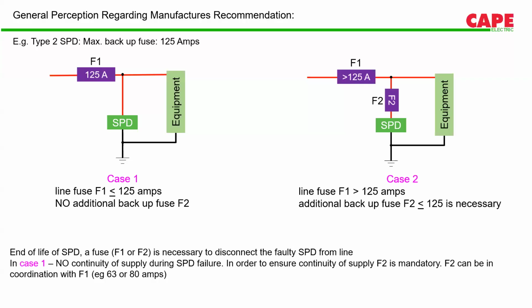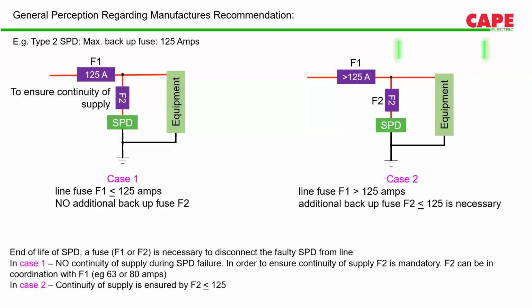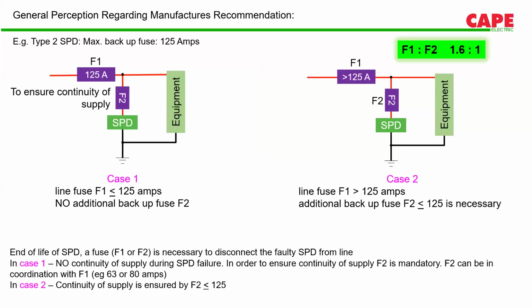Whereas in case number 2, once the SPD fails, only F2 will blow and F1 will remain in closed mode. So we get continuity of supply. So there are two things. One is priority to continuity of supply. Second is priority to continuity of protection. In case number 1, we are getting a priority to continuity of protection.